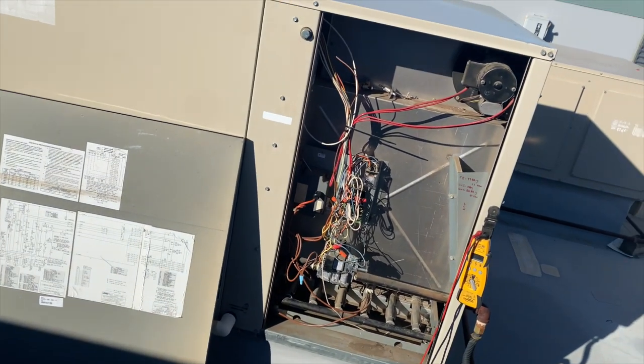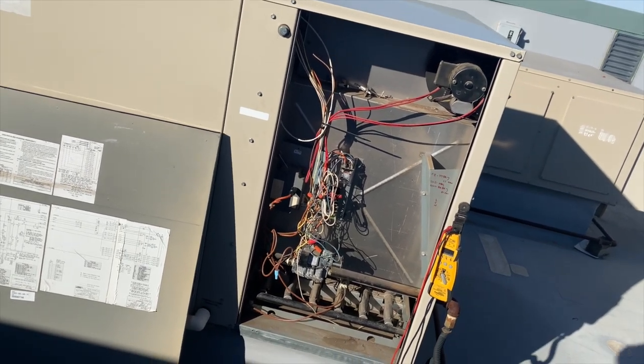We're going to power it up. Keep in mind that ignition control module, it's not going to spark immediately once it receives power. Typically there might be some kind of delay just to kind of let it do its thing, and then it'll spark and then it'll open up the gas valve once it detects the flame. Oh we got ignition! So it looks like we might have just had a bad connector. I'm going to still quote them for an ignition control module just in case because I was moving the wires around, so it could have just been loose connections.